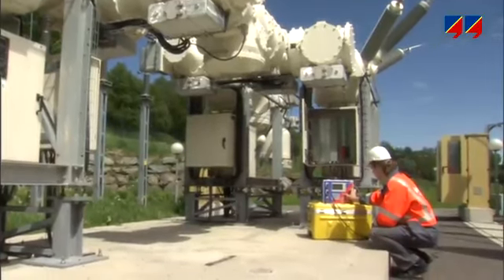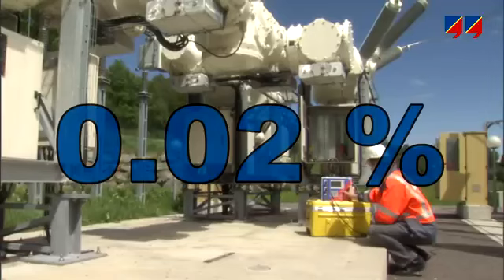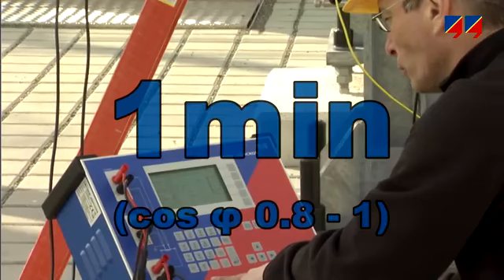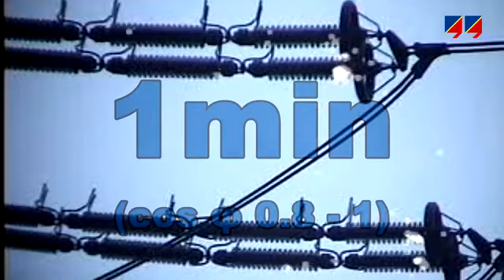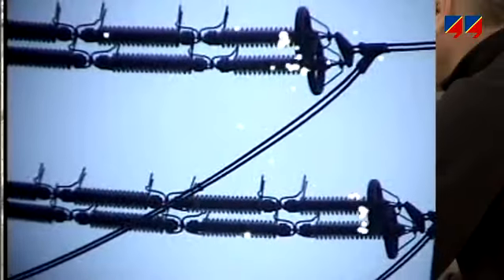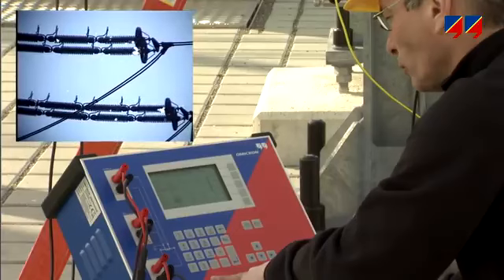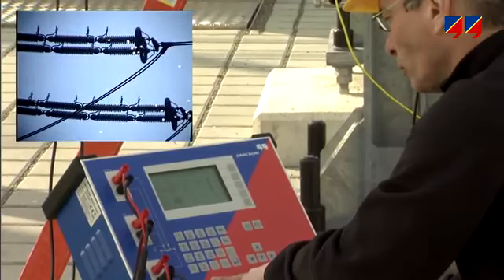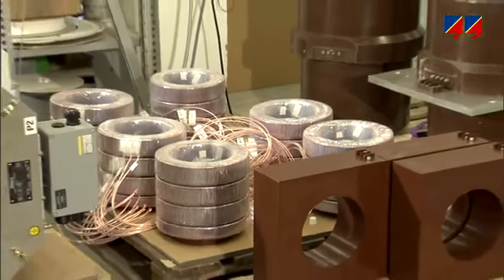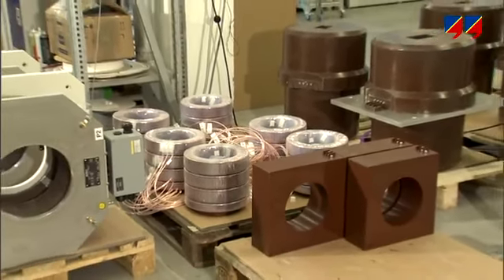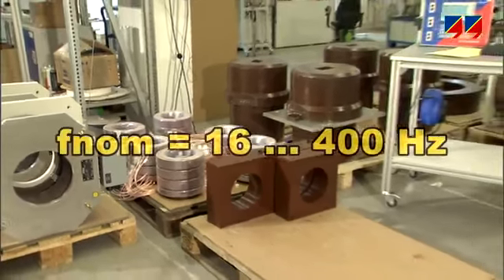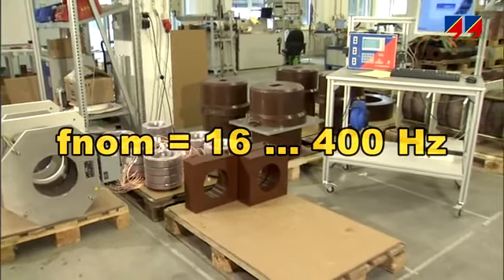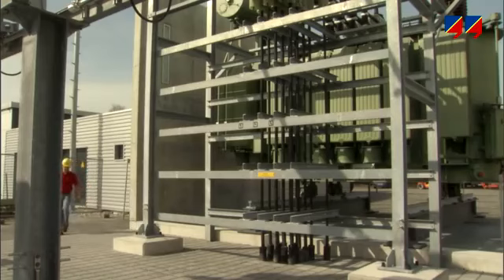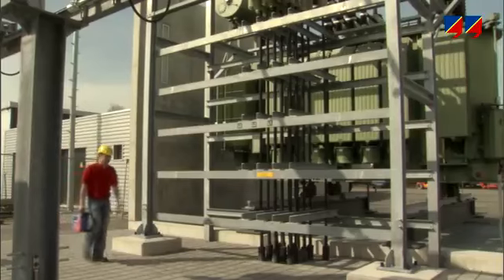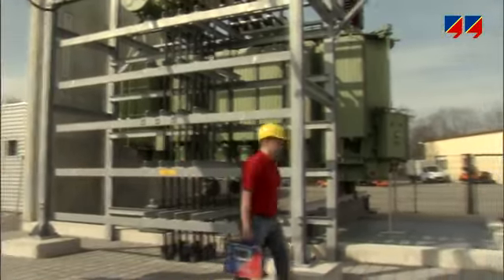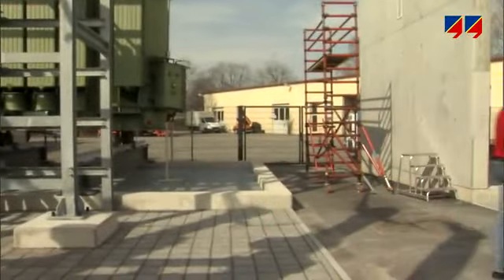CT Analyzer achieves an accuracy of 0.02% for ratios and 1 minute of 1 degree for phase angles, even in the presence of the electromagnetic disturbances common on site, and provides all of the important CT parameters. In addition to testing CTs for 50 or 60 Hz applications, CT Analyzer can also test any CT with a frequency rating from 16 to 400 Hz. CT Analyzer is a universal instrument suitable for measuring the parameters of current transformer types of any age.